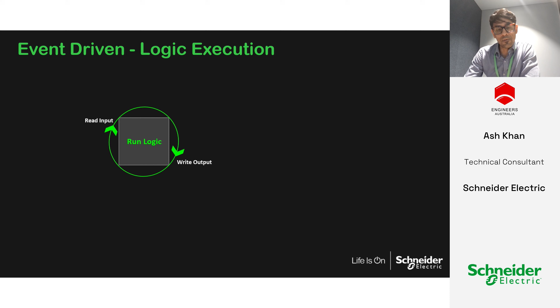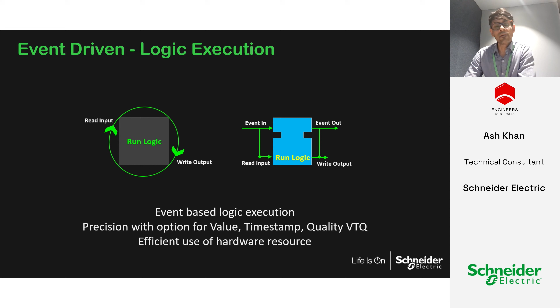So if the event changes, then the input is read into the block. The logic is then run, and based on the run logic, it will write an output and also pass on output events. Because you may be chaining these blocks together, an event will read the inputs, run the logic, write the output, and then that event output can go to the next block as an example. So event-based logic execution provides precision with options for value, timestamp, and quality, or VTQs, and efficient use of hardware resources. So it's not overrunning the hardware by running scans constantly.